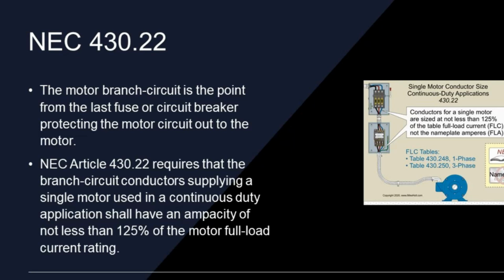So, now we know what the FLC is. We can use it to determine a couple of different things. I can use it to determine my conductor size, and I can use it to determine my ground fault and short circuit. Okay? So the motor branch circuit is the point from the last fuse or circuit breaker protecting the motor circuit out to the motor. Article 430.22 requires that branch circuit conductors supplying a single motor used in continuous duty application shall have an ampacity of not less than 125% of the full load current rating.